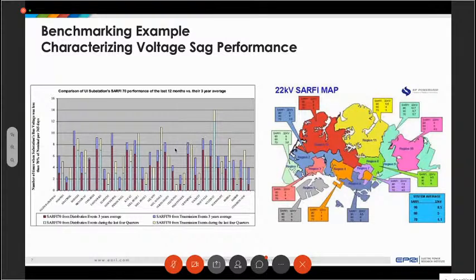And this chart illustrates the voltage sag performance over the last year, and right next to it is a bar that indicates the voltage sag performance over the last 3 years. So you can compare the last year to the last 3 years and see if it's getting better or worse. This is a utility that has relatively short feeders and low exposure to faults, so the voltage sag performance is very good. Voltage sags of, say, 4 to 10 per year is very good. That's some of the best in the world.